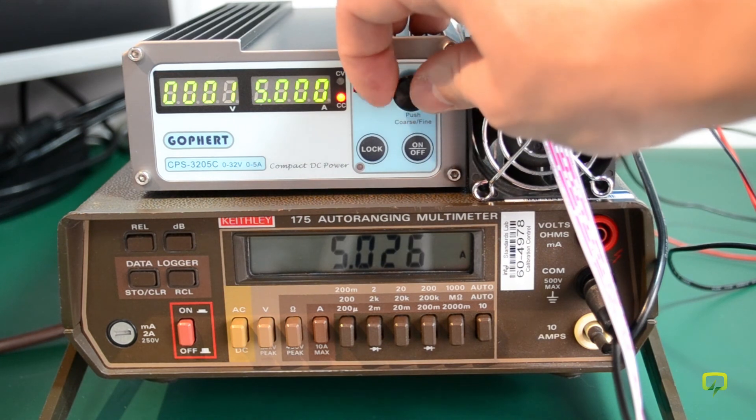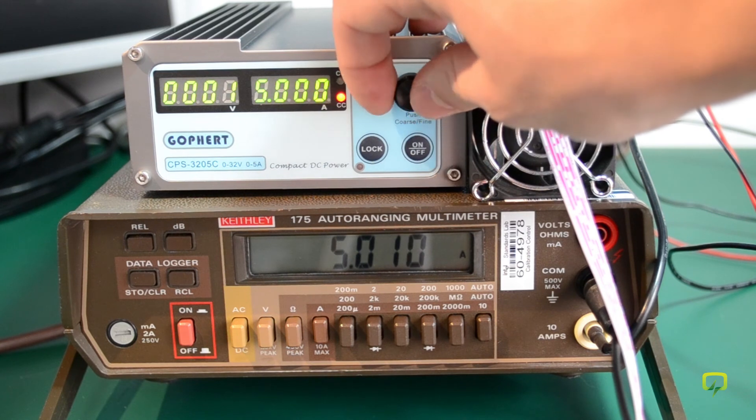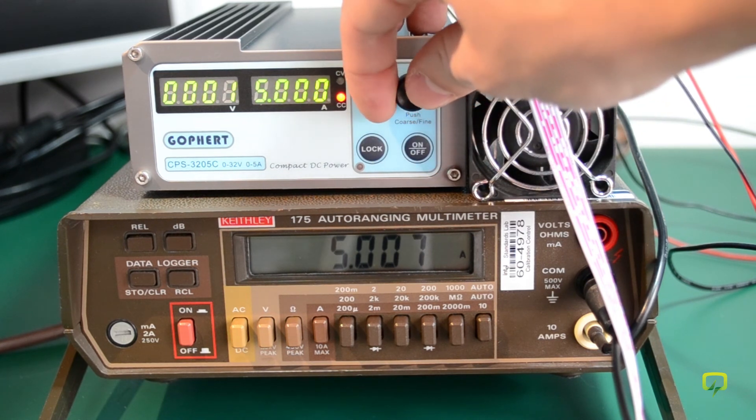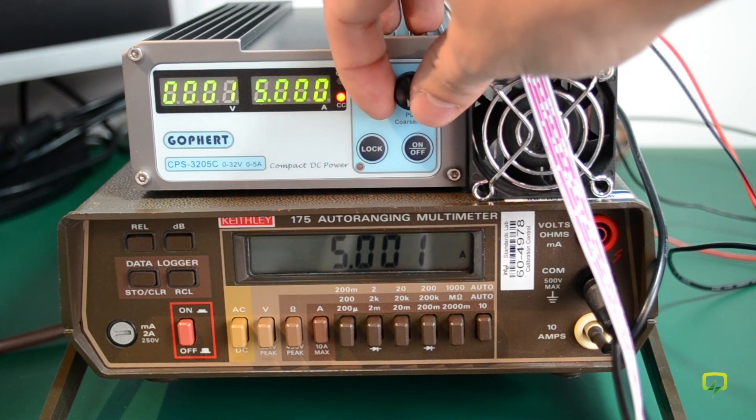I think one of the problems of this calibration is that it only has these two ranges for calibrating the ammeter: the 1 amp and the 5 amp. It should have been better if it also had a 500mA calibration range.